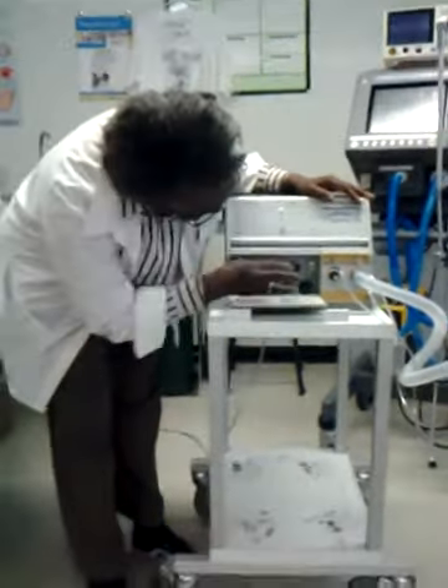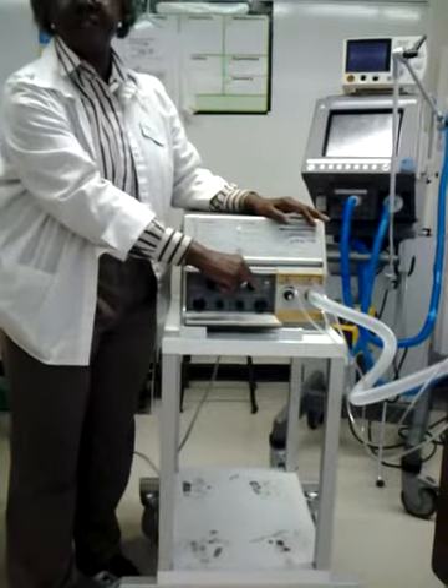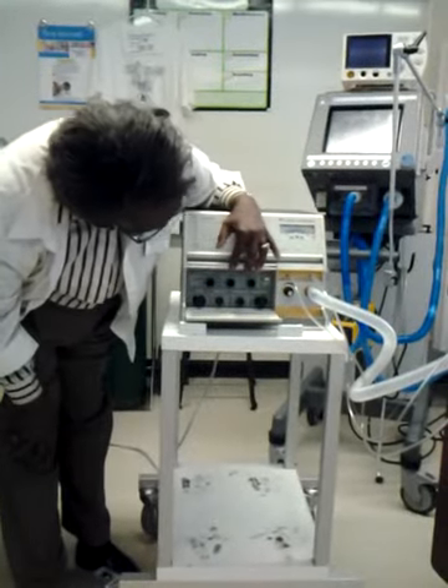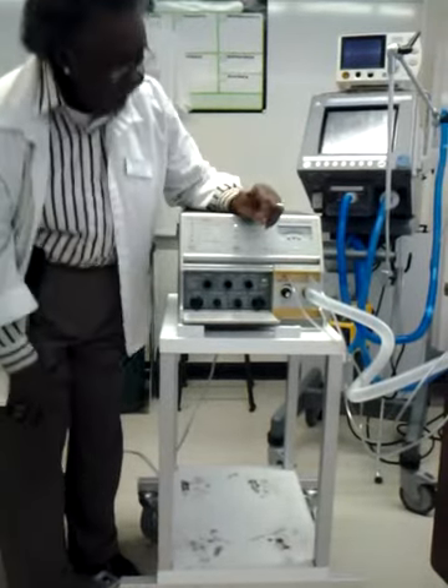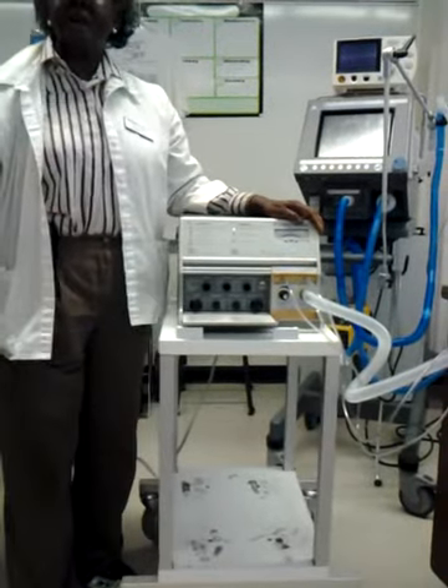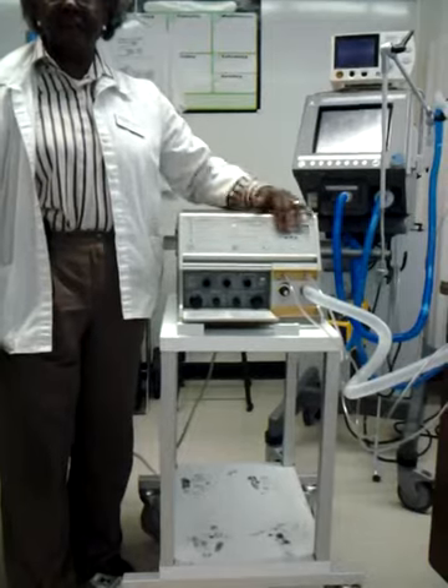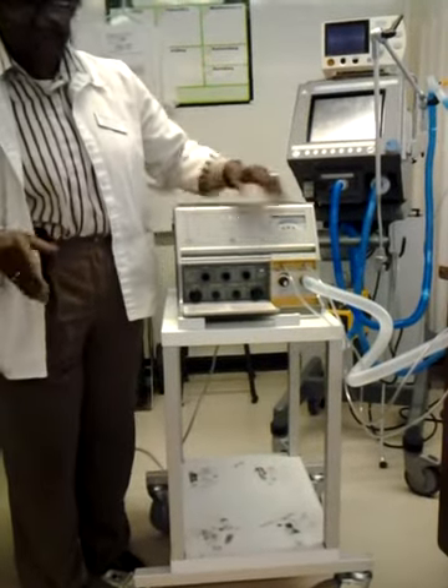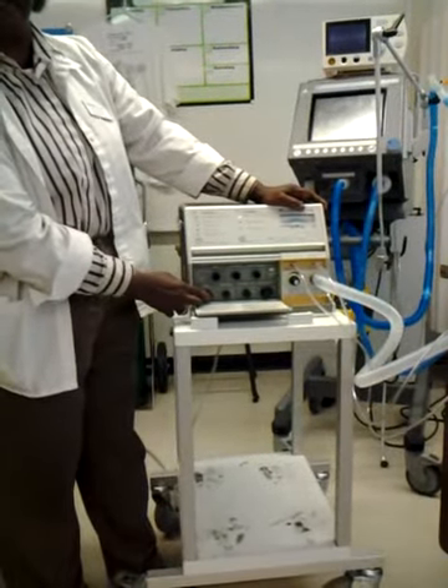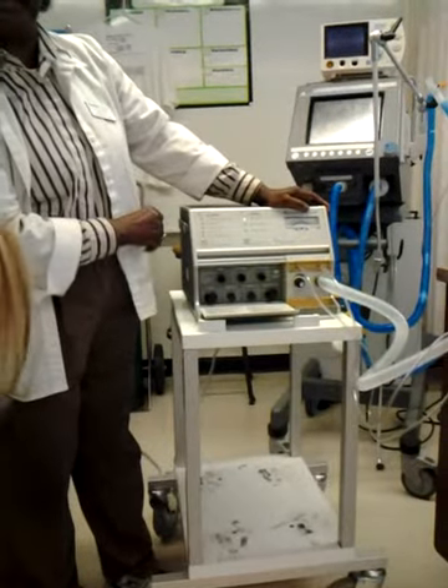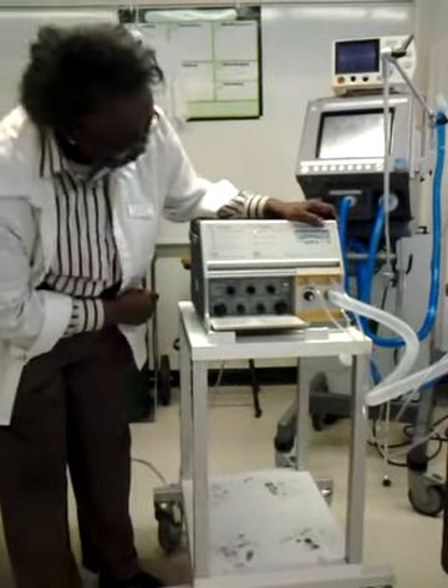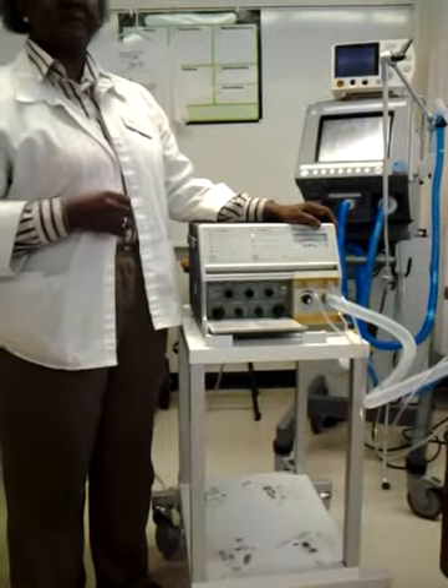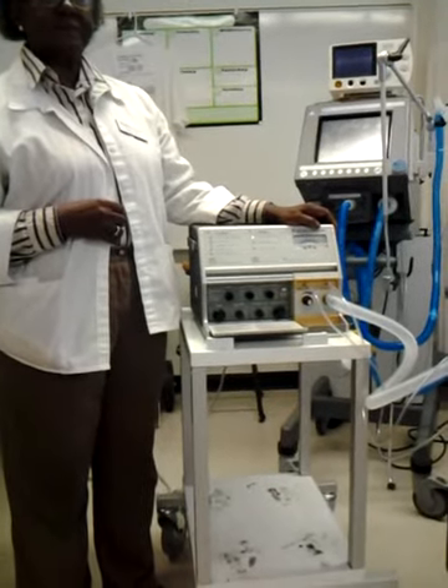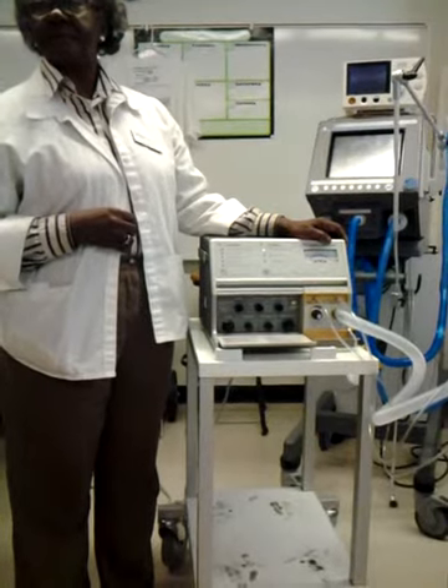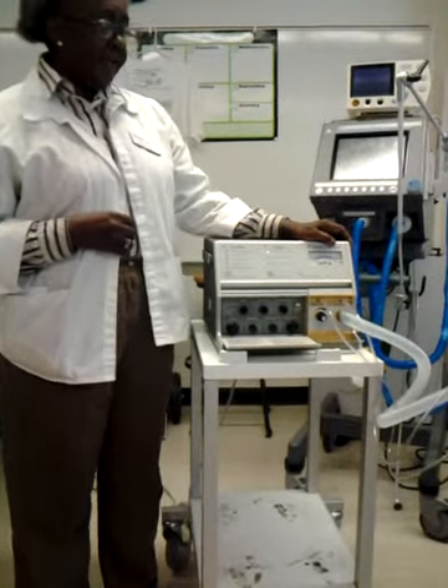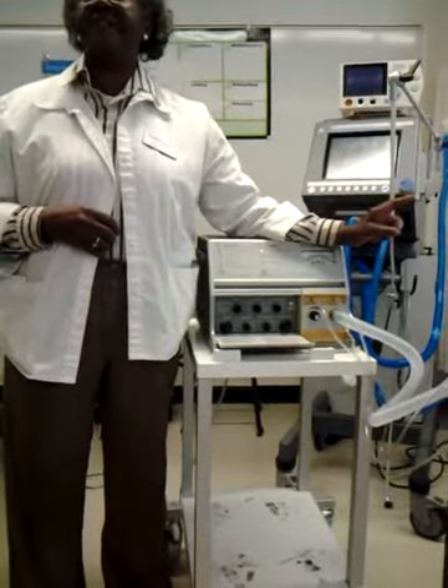The two buttons up here are your pressure alarm buttons. You have a high pressure alarm and a low pressure alarm. That's the only alarms? Well, you do have a low volume alarm, but you have to go into another menu. It can give you low volume, but it's not an alarm that you can set. It's internal. Okay. So the alarms are what? Again, I'm sorry. The high and low pressure. And the low volume alarm's internal. You have your PEEP valve on this device, which is external.